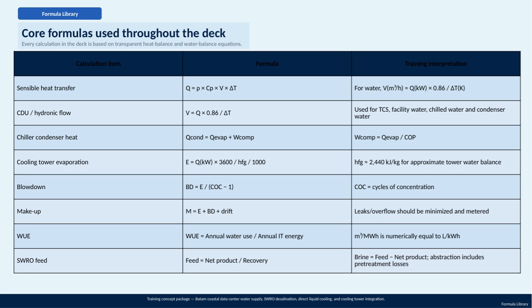We start with a sensible heat transfer formula, which calculates heat transfer in water using flow rate, heat capacity, and temperature difference. This is crucial for understanding how much heat energy is being moved within the system. The hydronic flow calculation is derived from this, allowing us to determine the volumetric flow rate of water or chilled water in different cooling circuits.